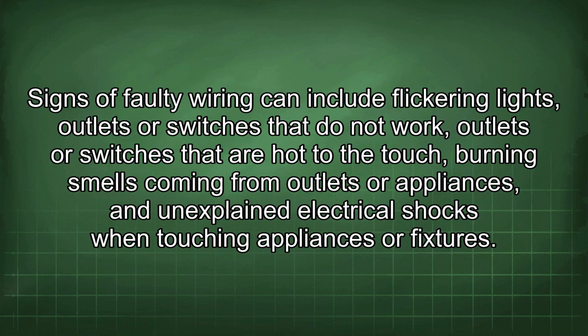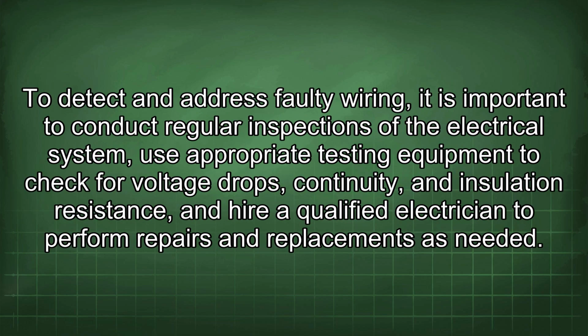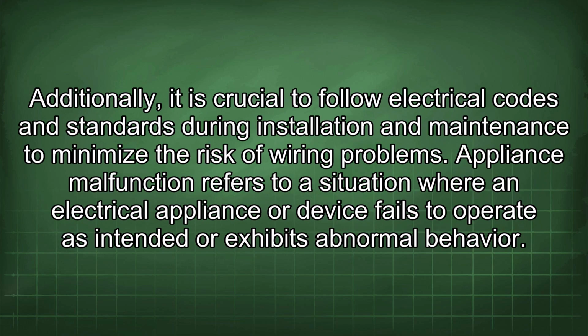Signs of faulty wiring can include flickering lights, outlets or switches that do not work, outlets or switches that are hot to the touch, burning smells coming from outlets or appliances, and unexplained electrical shocks when touching appliances or fixtures. To detect and address faulty wiring, it is important to conduct regular inspections of the electrical system, use appropriate testing equipment to check for voltage drops, continuity, and insulation resistance, and hire a qualified electrician to perform repairs and replacements as needed.